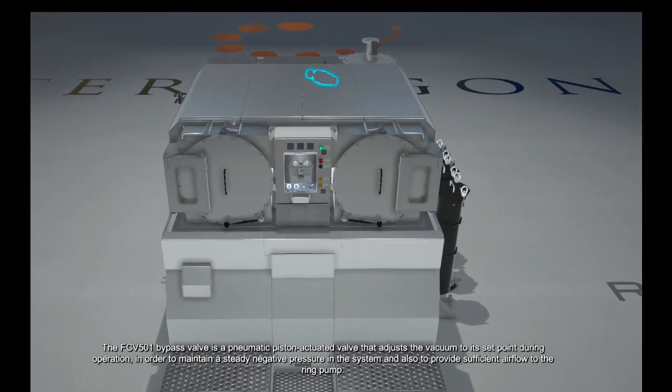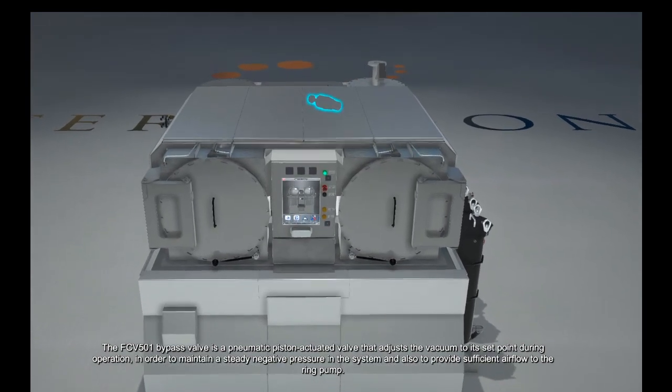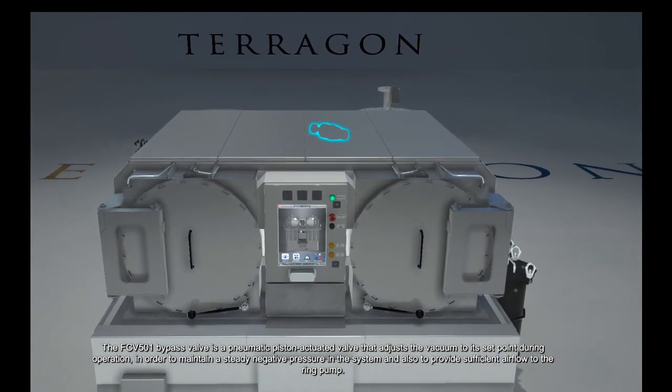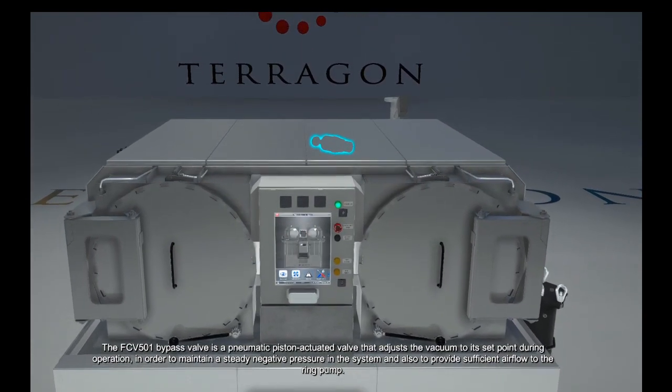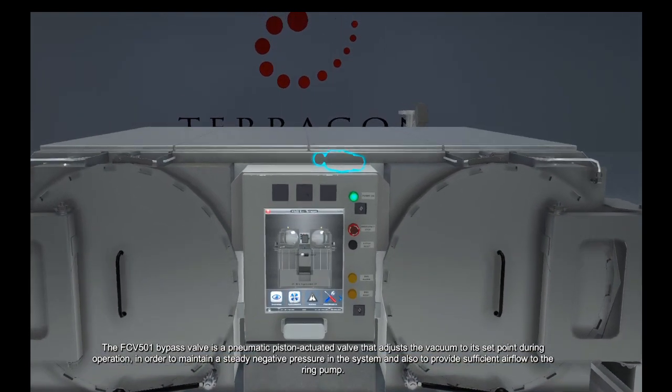The FCV501 bypass valve is a pneumatic piston-actuated valve that adjusts the vacuum to its set point during operation in order to maintain a steady negative pressure in the system and also to provide sufficient airflow to the ring pump.